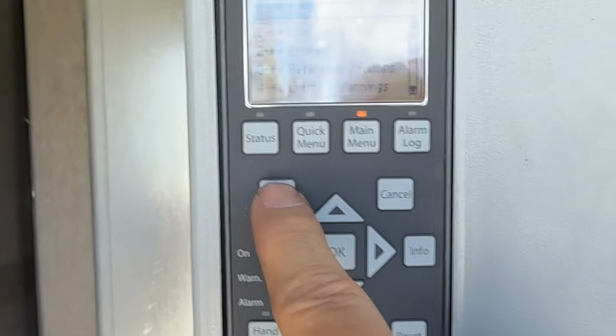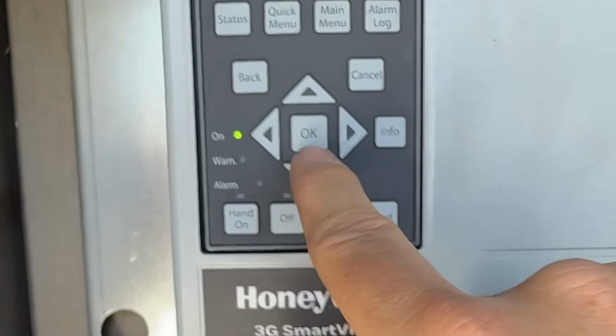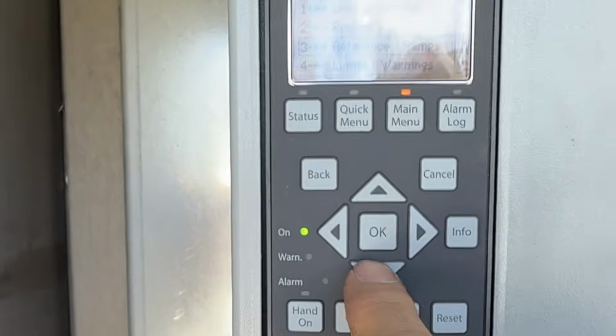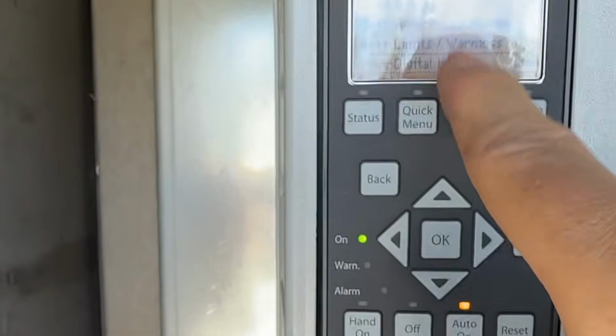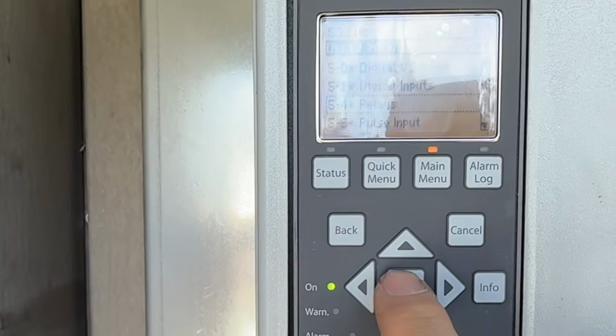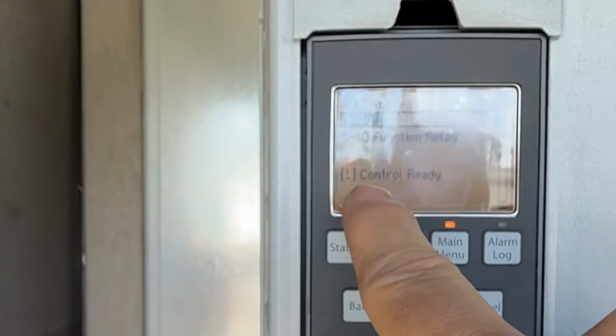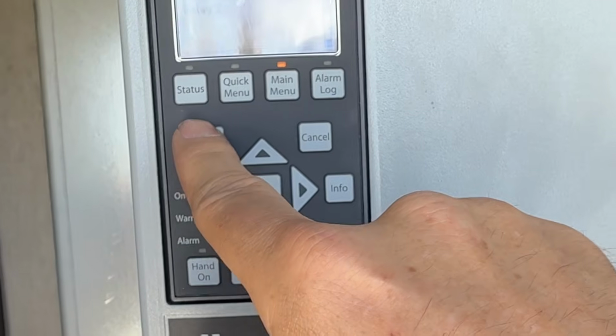One of the things I found out is for that alarm relay, you do need to go in and set it up. You go to the main menu, go to 5, digital in/digital out, then we go to relays, and relay 1 is the one we're using. We want to have it set up for control ready, and then it'll be good. Then you just want to back out all the way, and there we go.